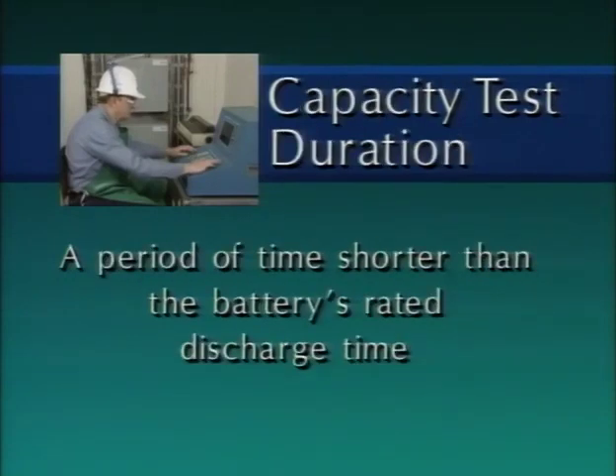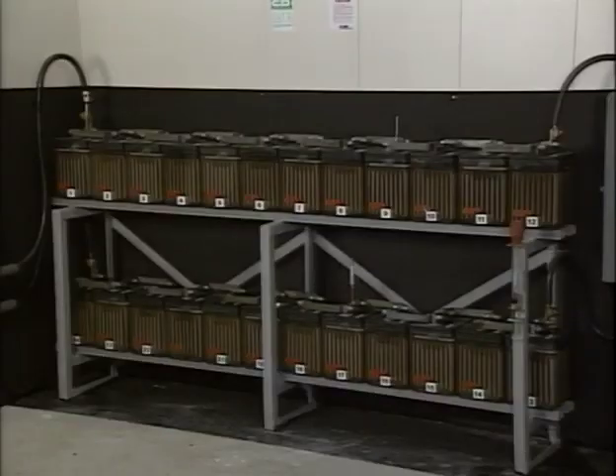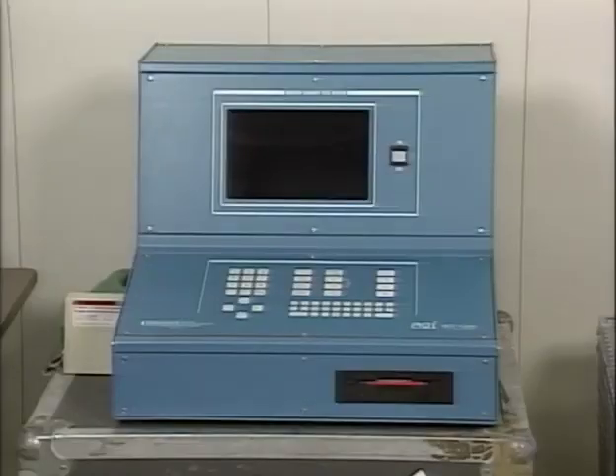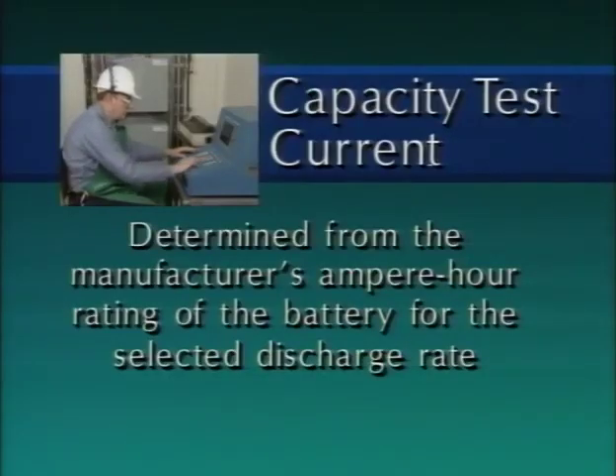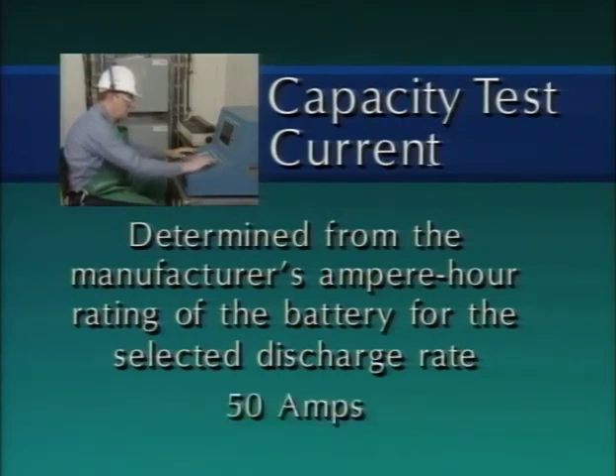For the capacity test, the duration of the test is a period of time that is shorter than the battery's rated discharge time. For example, this battery is rated to deliver 25 amps continuously for 8 hours before discharging to its minimum acceptable voltage. However, the control unit will be programmed for a 3-hour rate of discharge. The test current is determined from the manufacturer's ampere-hour rating of the battery for the selected discharge rate. In this case, the battery should deliver 50 amps continuously for the 3-hour test before discharging to its minimum acceptable voltage.